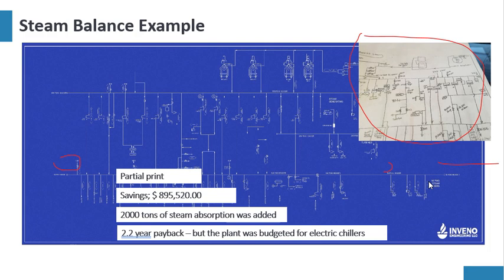Therefore, the savings was $895,520. The thing is, to consume the steam that's being vented to atmosphere, they had no use for low pressure steam. However, we implemented steam absorption units, and we put in about 2000 tons of steam absorption, which consumed the flash steam or the excessive steam that was being vented to atmosphere. Had a 2.2 year payback, but the plant was budgeted to put in electric chiller units anyway, so we shared the cost with that. It still ended up at 2.2 year payback. My point is that again, couldn't understand the dynamics of the system unless we did this steam balance.